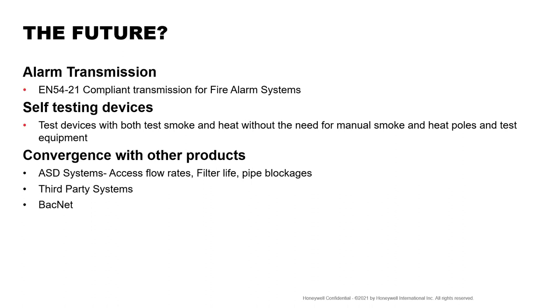Third-party systems we've spoken about. BACnet, I mentioned BACnet and Modbus running through BMS systems is an important one. There's the Modbus one. Voice alarm and public address systems. Now, voice alarm is coming on much more into the marketplace rather than having electronic sounders and whatever, because with a voice alarm, people are going to react better if they hear a message that says, bing bong, a fire has been detected on the third floor. You're going to react differently than if you just hear a siren going off in the background. It's telling you what to do. It's telling you there's a fire. It's advising you to leave via the nearest exit.